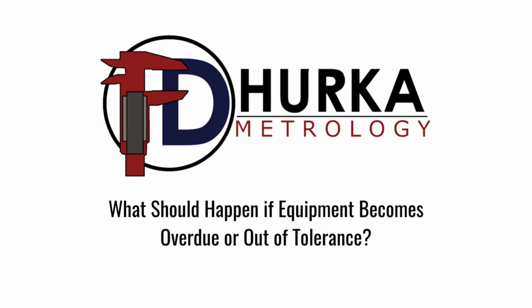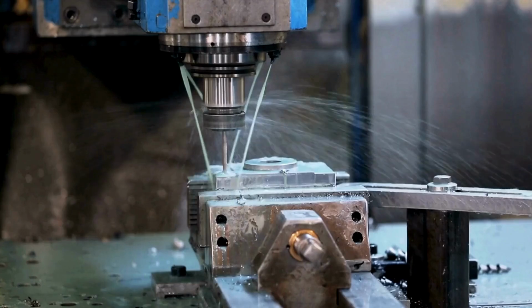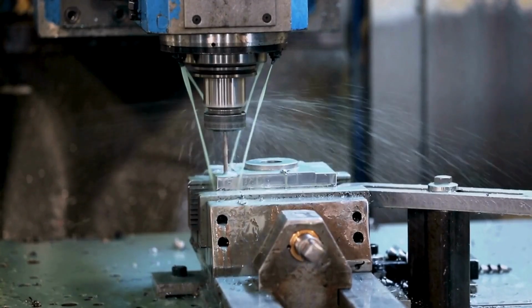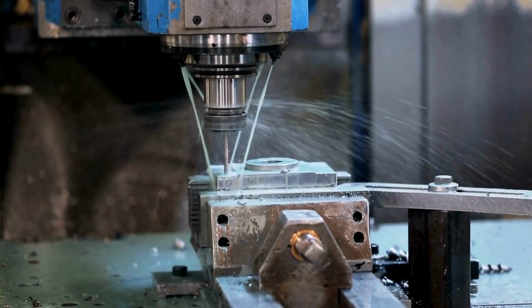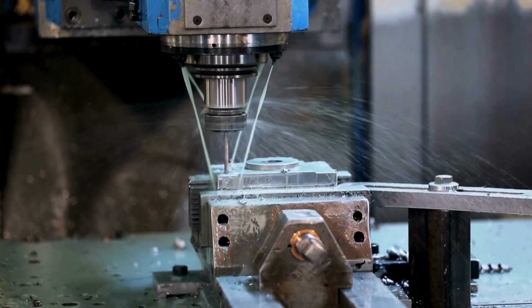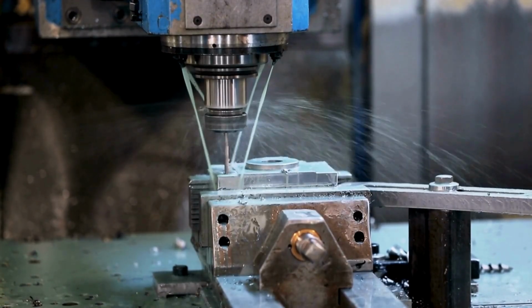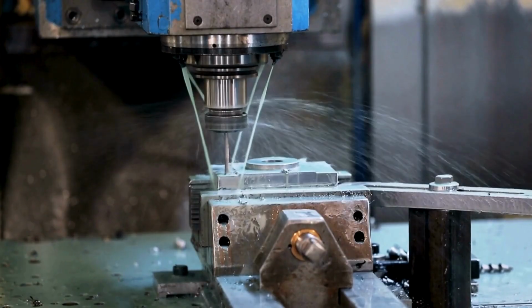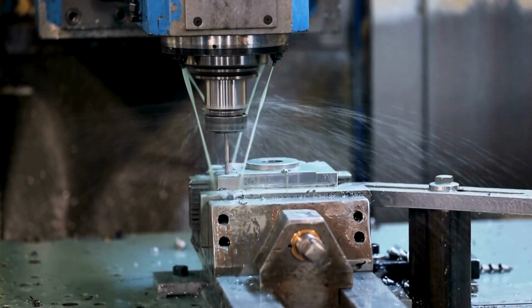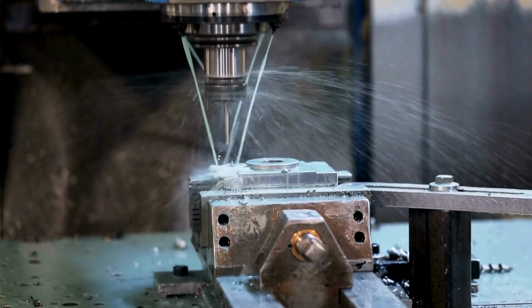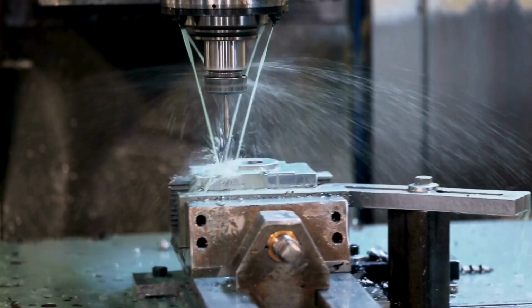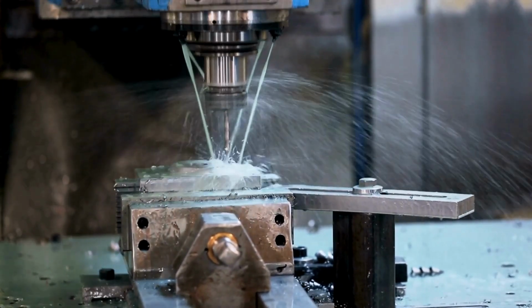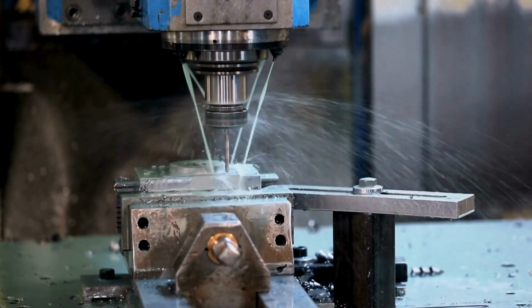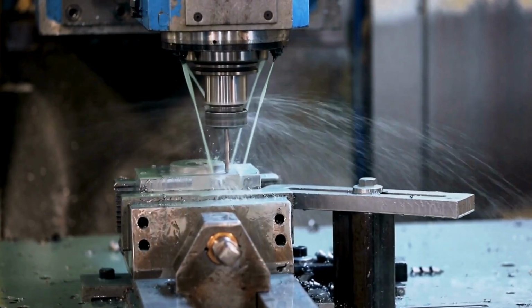What should happen if equipment becomes overdue or out of tolerance? The facility should have a documented process for removing, reviewing, or restricting that equipment and determining whether any recent measurements or products may have been affected, because these decisions should never be improvised under pressure, and an effective calibration schedule works best when the response rules are already clearly defined.